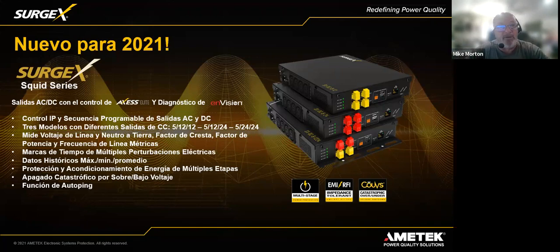These particular outlets give you substantial current. If you're dealing with all 12 or all 24, you're going to have a 5 amp output. If you're dealing with a combination, each one of these will have a 3 amp output, and this is 2 banks of 2 each. These are totally, fully IP addressable - the AC section, all 4 outlets, are totally, fully IP addressable as well.